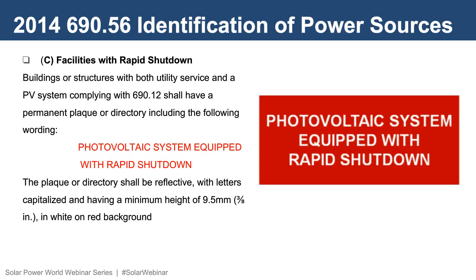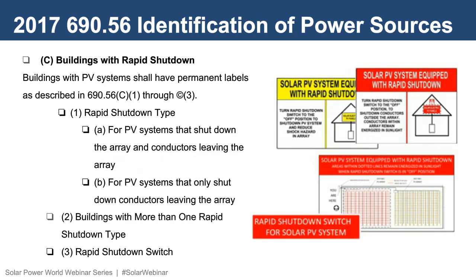The 2014 labeling requirement for rapid shutdowns is quite simple. A label stating "PV system equipped with rapid shutdown" is required. The 2017 identification of power sources labeling requires much more detail to be provided. First, the rapid shutdown type must be presented. Types include systems that shut down the array and conductors leaving the array, and the second would be systems that only shut down conductors leaving the array.